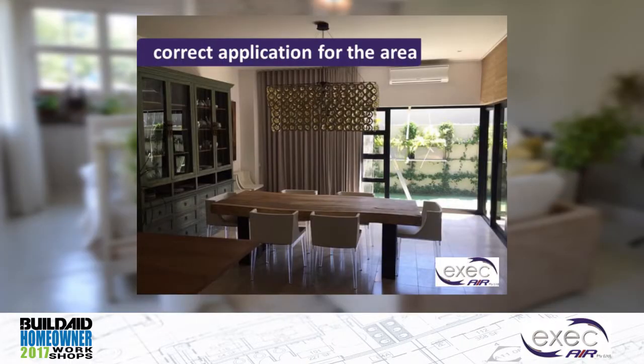Two things in response to that. One is there's an electrical connection, which you're not allowed to make unless you're an electrician. And the other one is, Werner, you guys will work out which unit to use for a certain space or certain volume. That is correct, yes. Obviously, you can work out on a calculation of about 150 watts per square meter if you do wish to size it yourself. Alternatively, a better idea would be to get a design consultant involved as well, because they can do the necessary calculations and then specify a unit that will be suitable for the application.